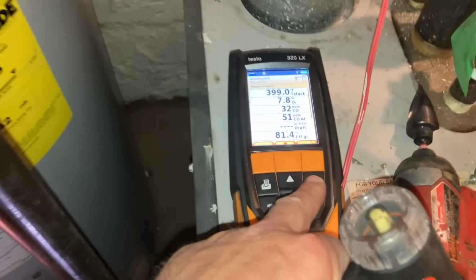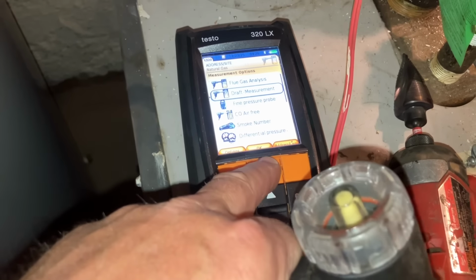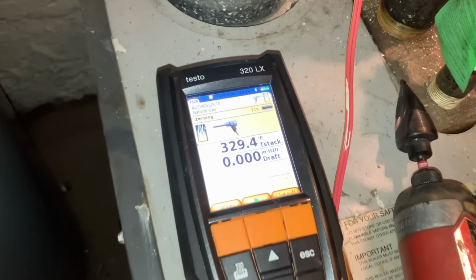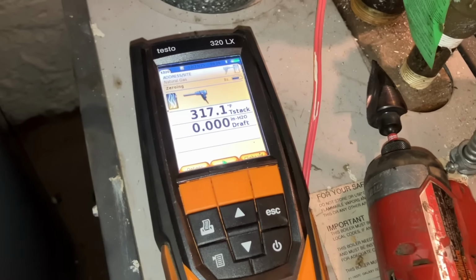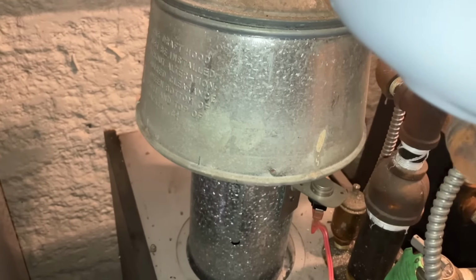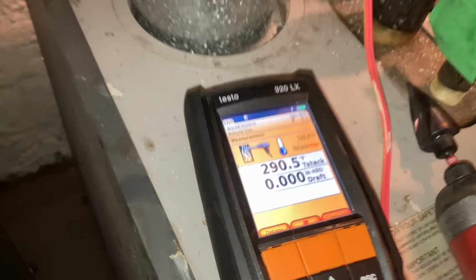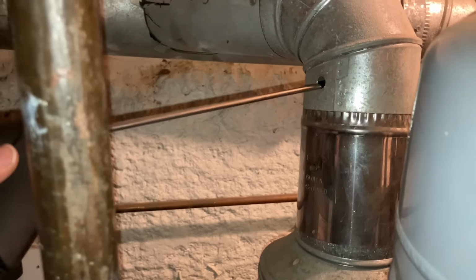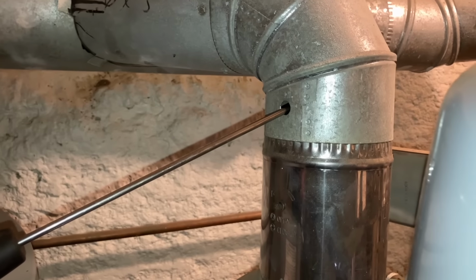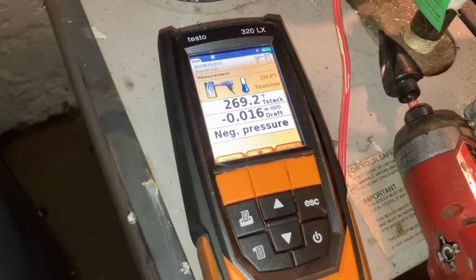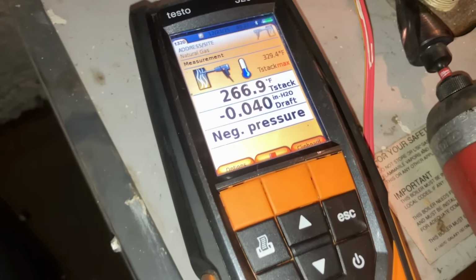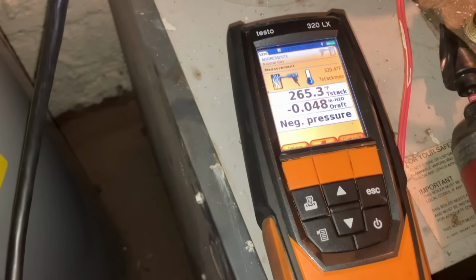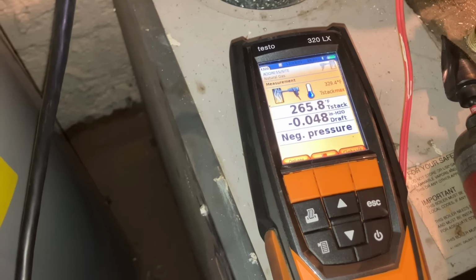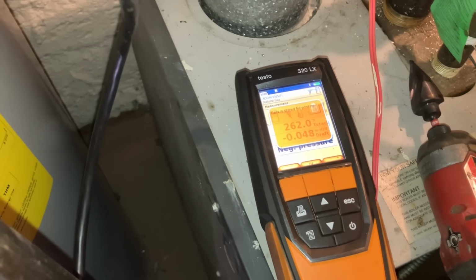We're gonna pull the probe out. We're gonna hit escape. We're gonna go to draft measurement. Hit play. It's gonna zero out from 11 seconds, and then we're gonna take a draft reading above the draft diverter in another hole that we drilled. Wait for it to zero out. Again, center of the flue. And we're looking for that negative pressure, which we have. Now this temperature is going to be lower than the one below the draft diverter, which is that piece right there. And once she's at a stable temperature, we'll clipboard that as well. And then we'll print the results to the printer.